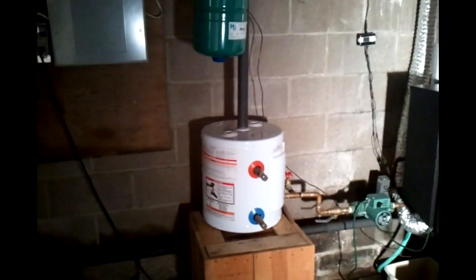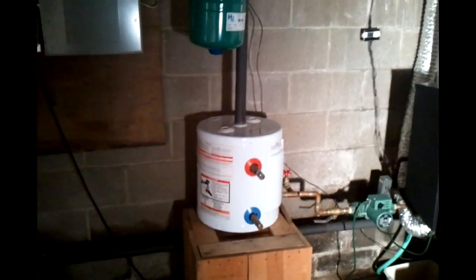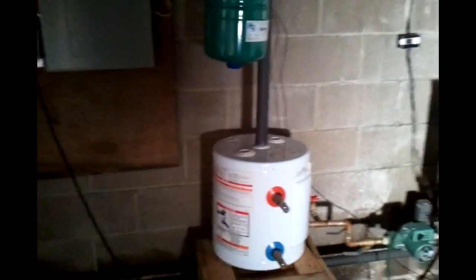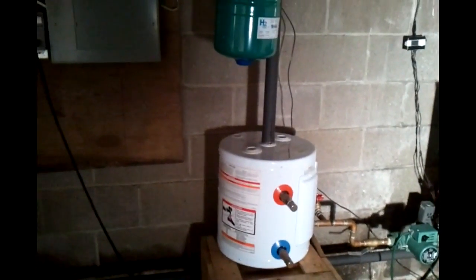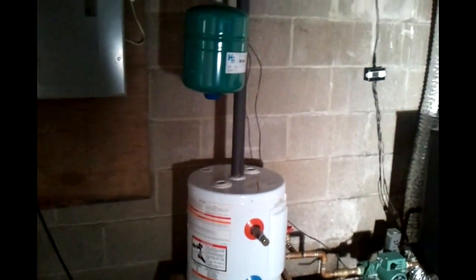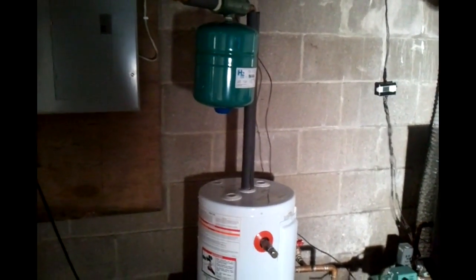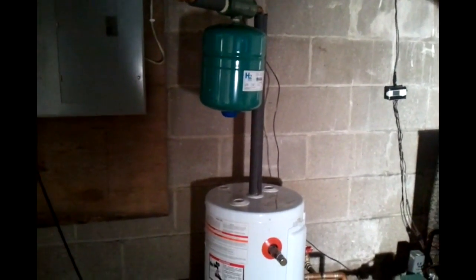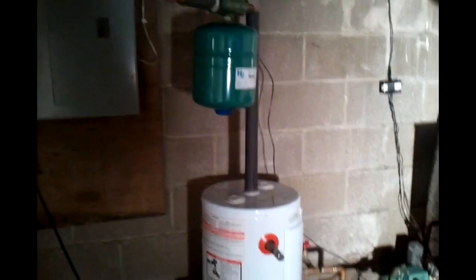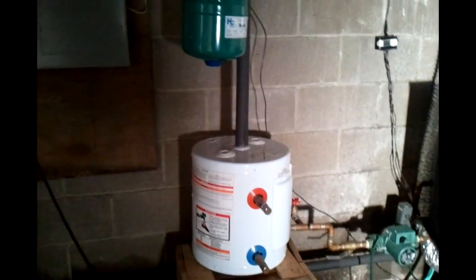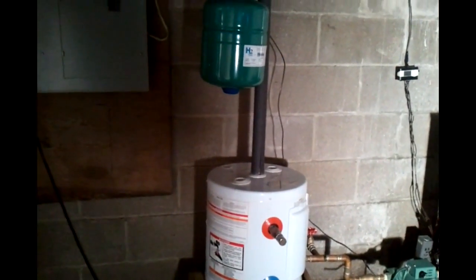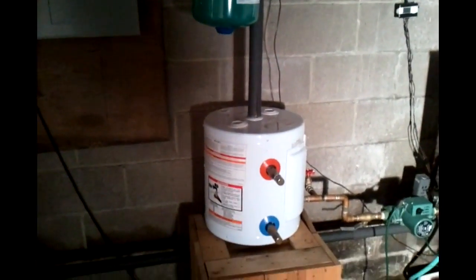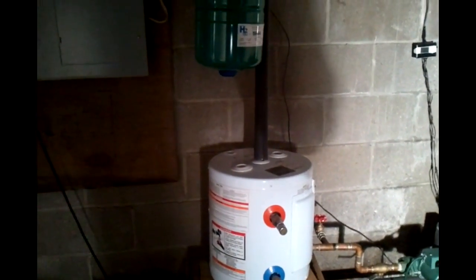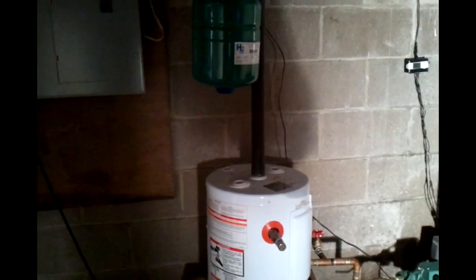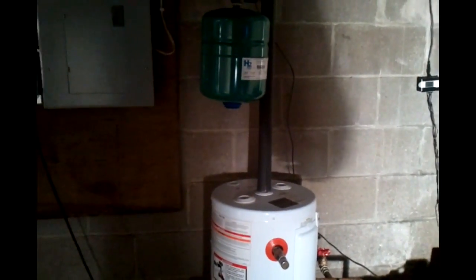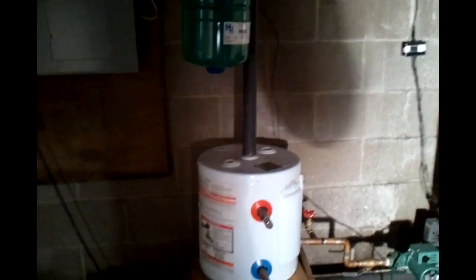Now for the operation of the system, we'll start with the 6-gallon tank. This is optional. The purpose of this is to mix the hot and cold water, the incoming water and the outgoing water, before it goes into the corn stove. And it's also used just to have a volume of water. You need a good volume of hot water to run through the furnace. In certain setups, this is not needed. If you're running a radiant floor, you already have enough volume, so you wouldn't need this 6-gallon tank.